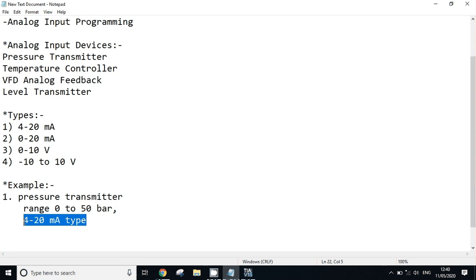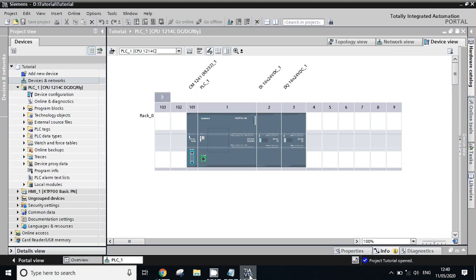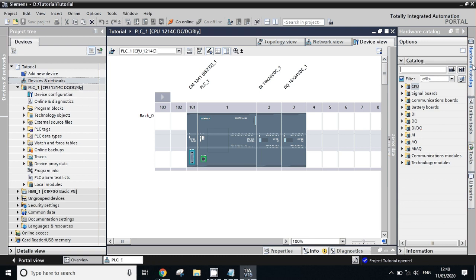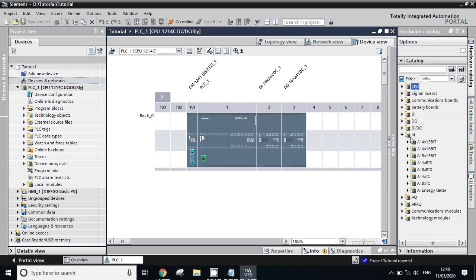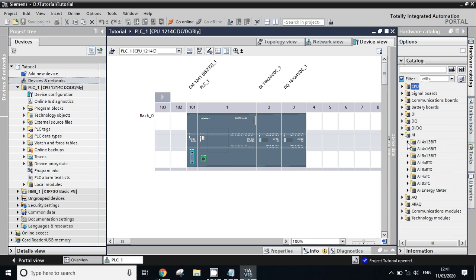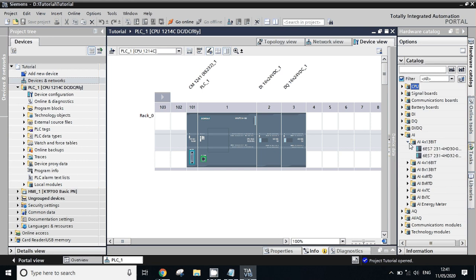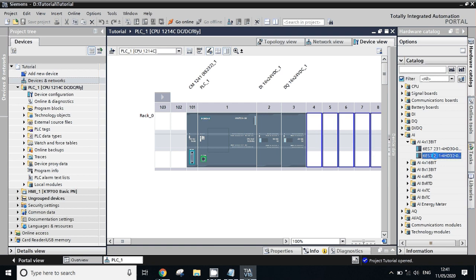Let's start the lesson for TIA Portal. Open TIA Portal. The very first thing we need to do is add an analog input module in our device configuration. Go to hardware catalog, go to AI analog input. These are the types of analog input cards. First is 4 into 13 bit, which means 4 channel. This is also 4 into 16 bit - the bit means it shows the resolution. Based on your catalog number, you have to select the proper catalog number from these configurations. This is RTD cards, this is TC cards, and this is for energy meter. We'll select our type - I will select 4 channel 13 bit because I have this hardware. Drag and drop here.